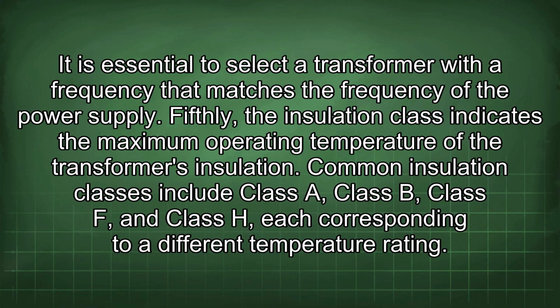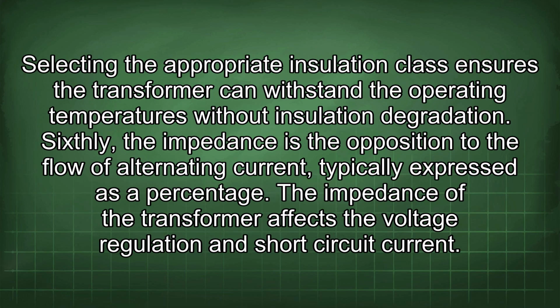Fifthly, the insulation class indicates the maximum operating temperature of the transformer's insulation. Common insulation classes include Class A, Class B, Class F, and Class H, each corresponding to a different temperature rating. Selecting the appropriate insulation class ensures the transformer can withstand the operating temperatures without insulation degradation.